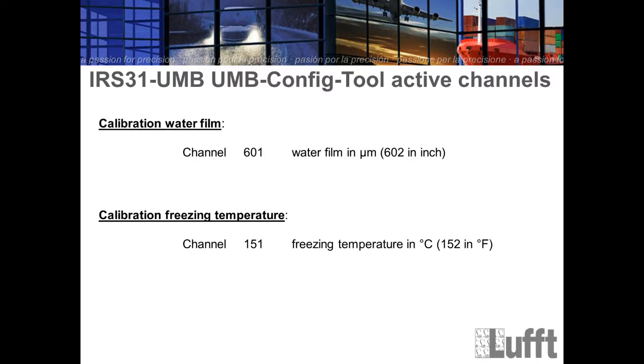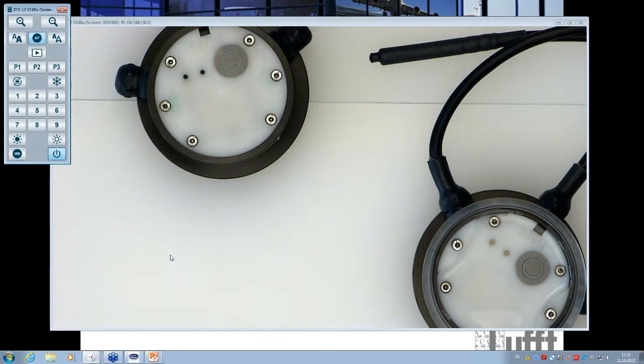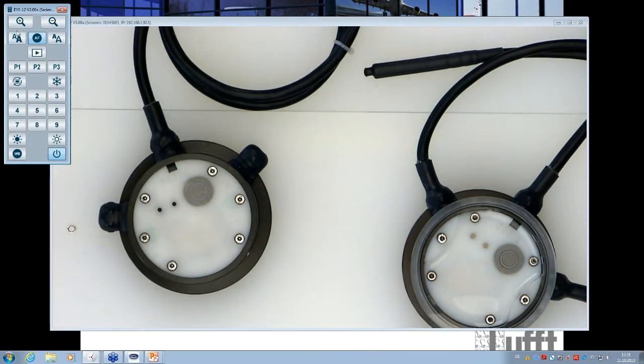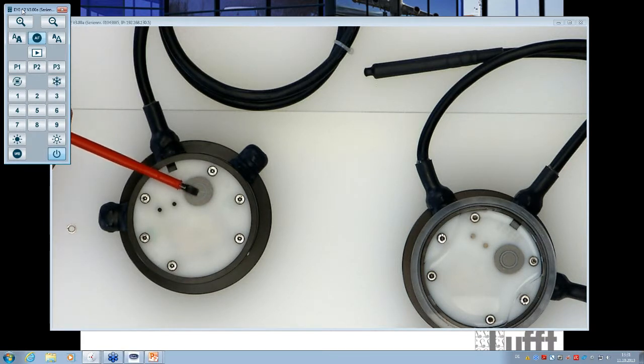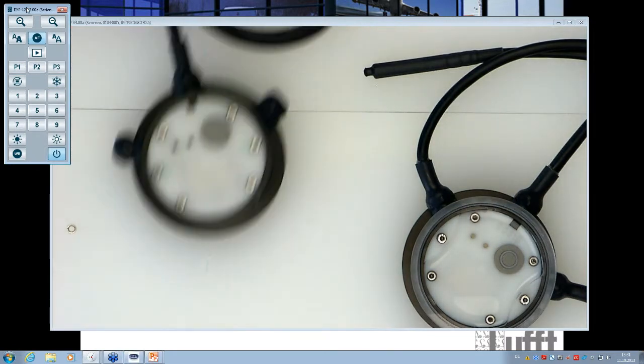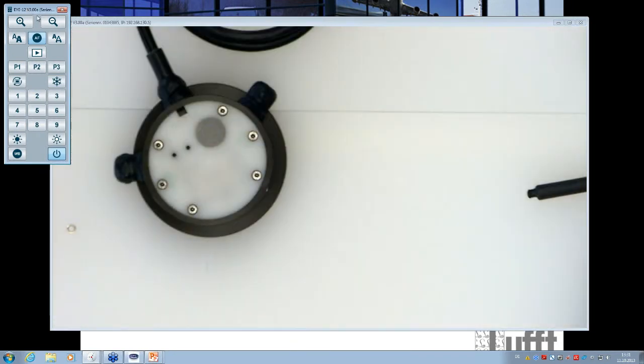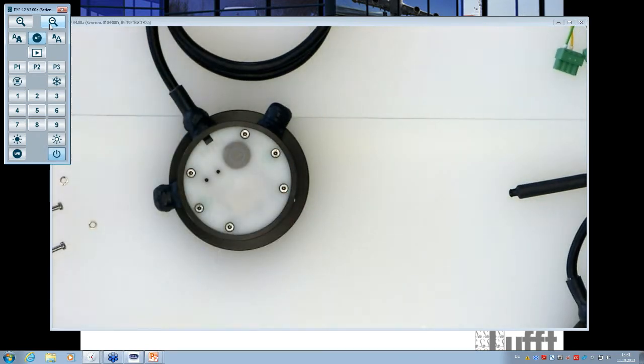Of course, remember, you can also in addition check the outside or the surface temperature, using a special external device, for example a handheld from Lufft or any other handheld or measurement device which is calibrated, and you can easily check the temperature using the probe. For example, this is the probe of the external device. You can put the probe on the surface, and then you can compare the value of the road sensor with the value of the probe, and they must be inside the technical specification. That's all you need to do. That's really easy, right? And then also the surface temperature is checked. Okay, I think that's all for the calibration.